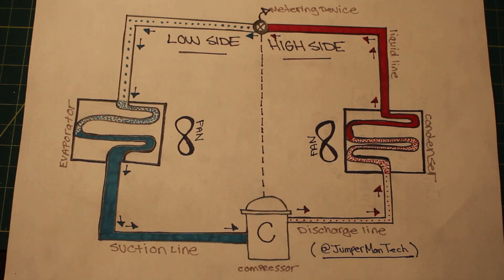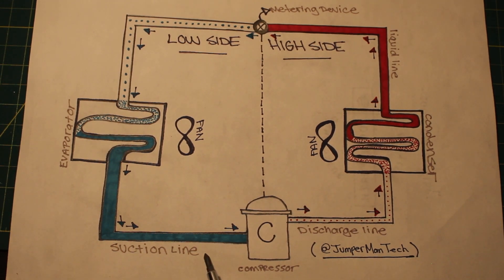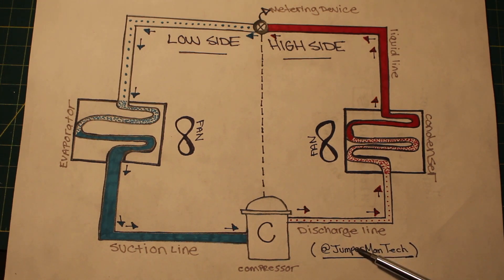To begin our lesson, we're going to start with our compressor. A compressor is both a motor and a pump that compresses refrigerant and moves it throughout the system. Refrigerant enters through the suction line as a low-pressure, low-temperature, superheated vapor, and exits through the discharge line as a high-temperature, high-pressure vapor as refrigerant is compressed.